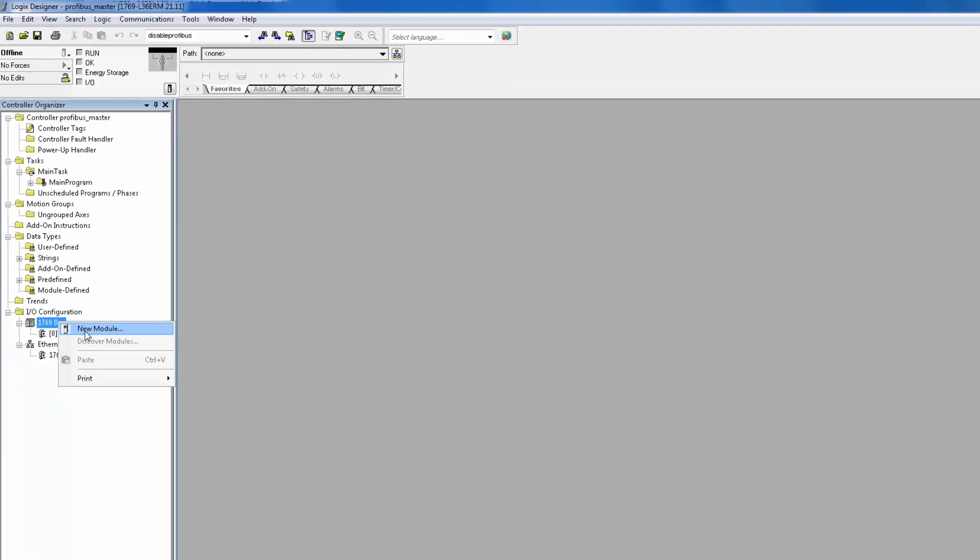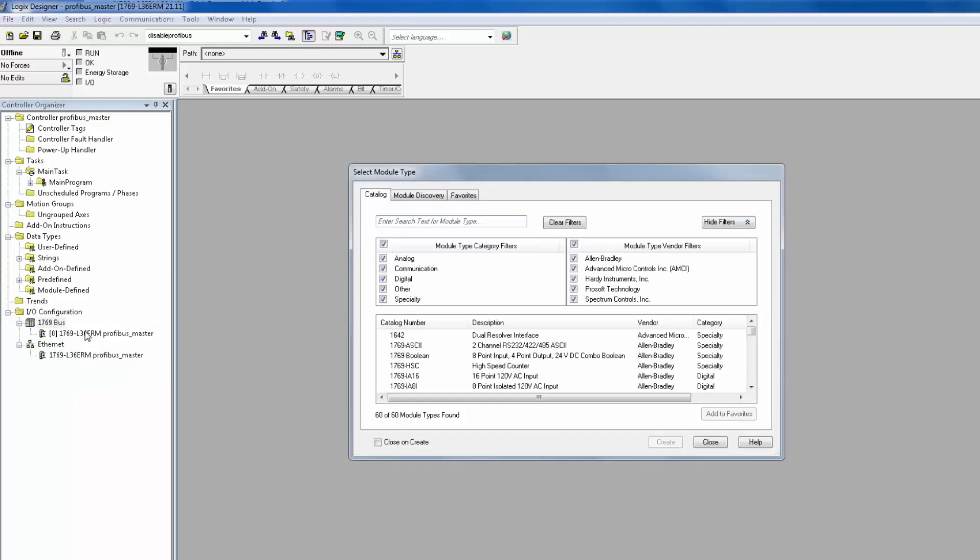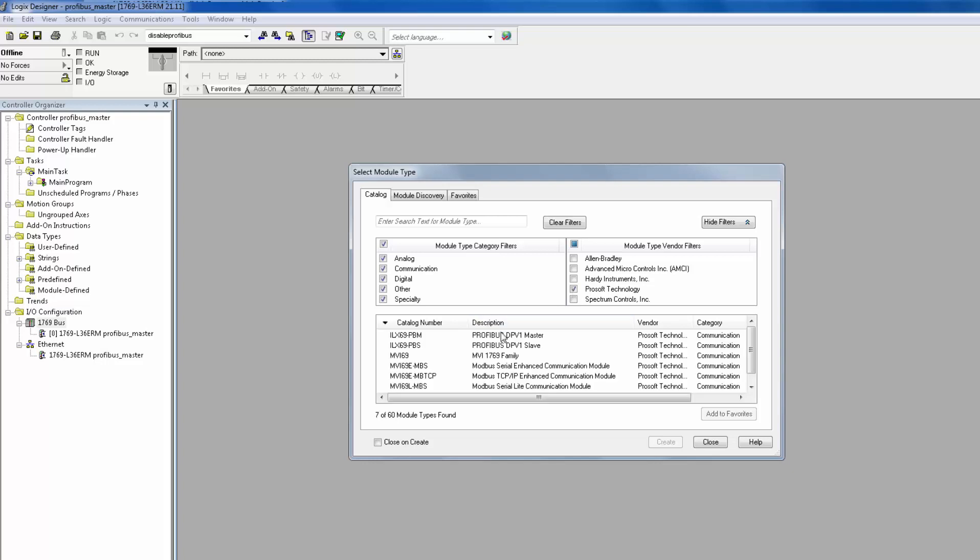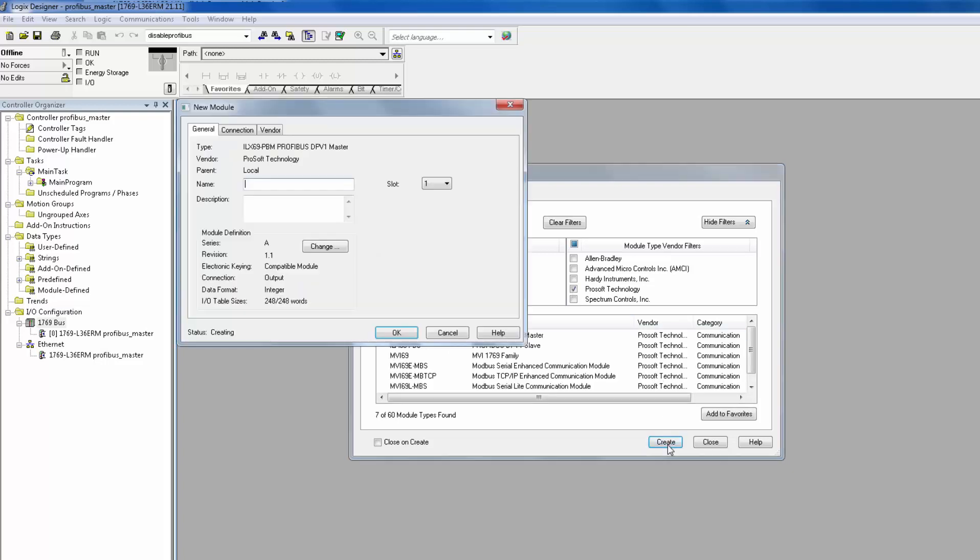First, we will add the module to the backplane by right-clicking on the 1769 bus and choosing New Module. Uncheck all vendors and check only the ProSoft Technology vendor. Then choose the ILX69 PBM and click Create. Give your module a name. I will choose PBM. Once completed, click OK.